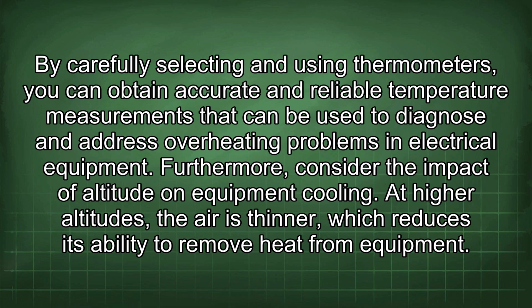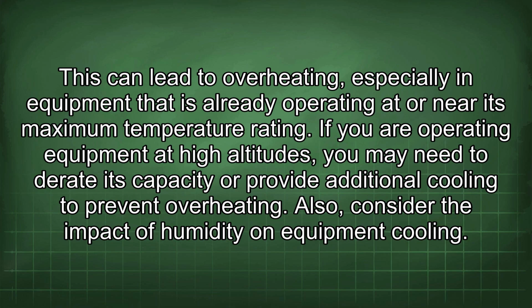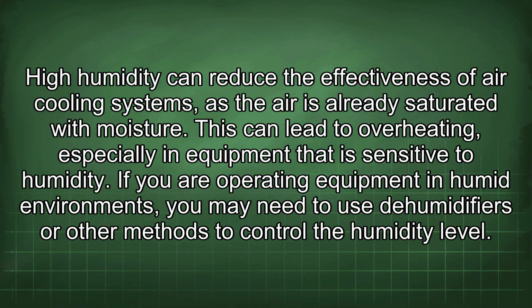Furthermore, consider the impact of altitude on equipment cooling. At higher altitudes, the air is thinner, which reduces its ability to remove heat from equipment. This can lead to overheating, especially in equipment that is already operating at or near its maximum temperature rating. If you are operating equipment at high altitudes, you may need to derate its capacity or provide additional cooling to prevent overheating. Also, consider the impact of humidity on equipment cooling. High humidity can reduce the effectiveness of air cooling systems, as the air is already saturated with moisture. This can lead to overheating, especially in equipment that is sensitive to humidity. If you are operating equipment in humid environments, you may need to use dehumidifiers or other methods to control the humidity level.